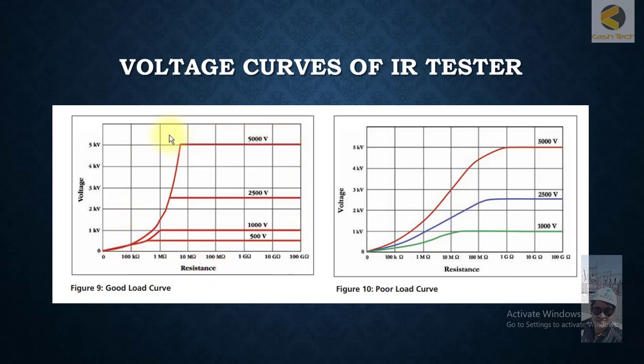The insulation here is healthy. But if the curve is slowly rising and the shape is like this of the applied output voltages of the testing equipment, then it means the insulation healthiness is not good. So this is another method to determine the insulation quality and insulation healthiness. Thank you.